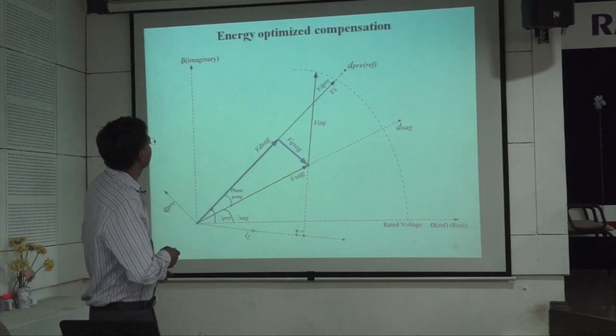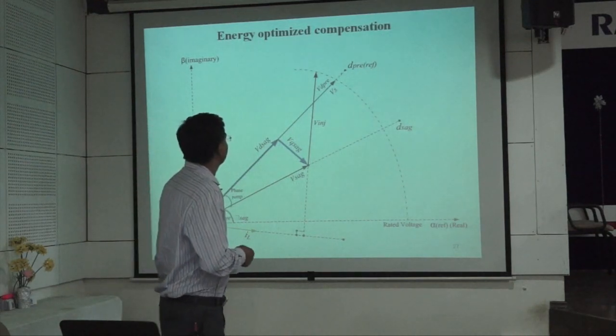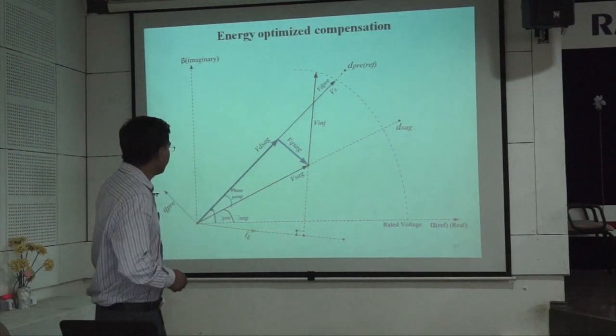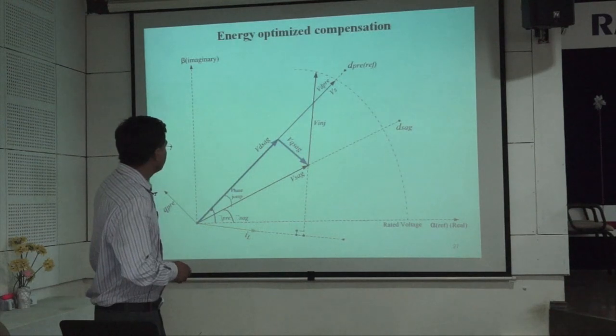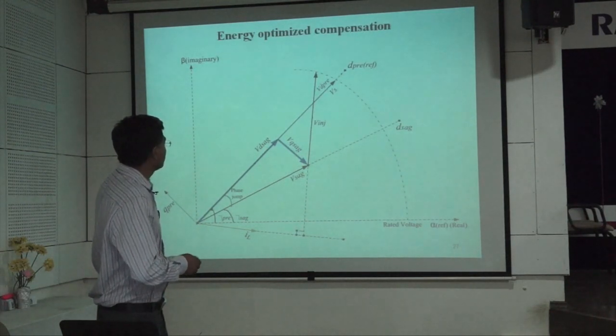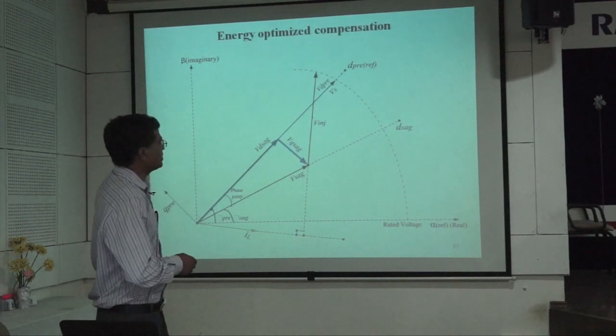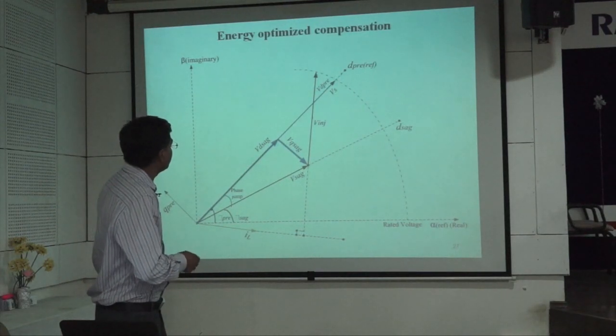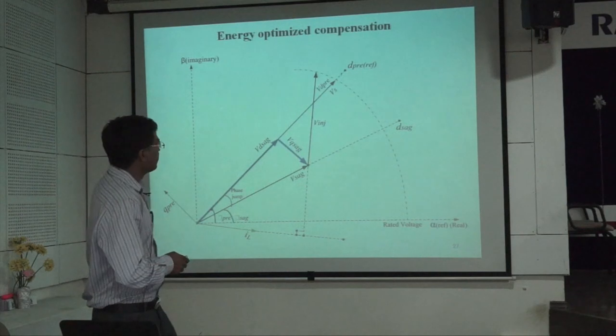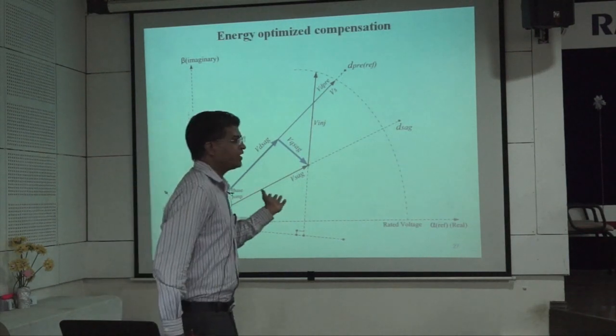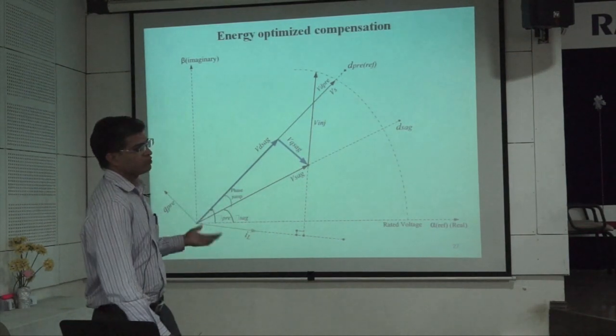So that's why there is another method, energy optimized compensation. We can compensate at 90 degrees. See, this is the sag in the voltage. We can compensate at 90 degrees to current. So this is the only reactive power compensation. So there is an increase in the voltage injection, but we don't require any active power injection into the system.